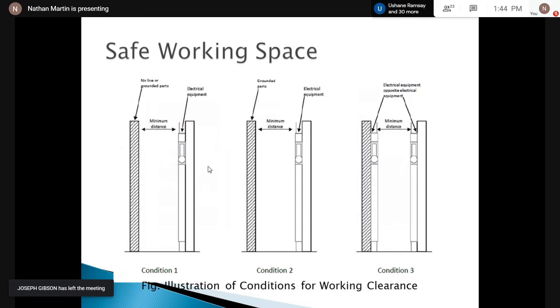So we'll put some distance in condition 1, condition 2, and condition 3. What does this mean? Condition 1 means you have electrical equipment on one wall, so no live or grounded parts on the other wall. Condition 2 is when you have the electrical panel but probably some metal parts on the other wall that need to be grounded. Condition 3 is where you have live electrical parts on both sides. Some panel rooms in large facilities will look like condition 3, and there are certain clearances we must observe.